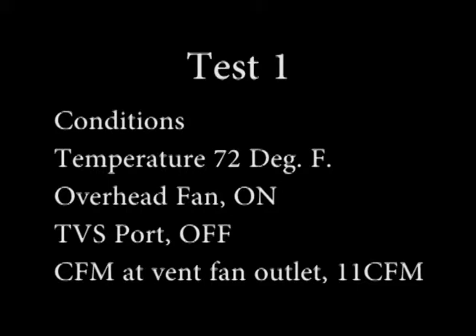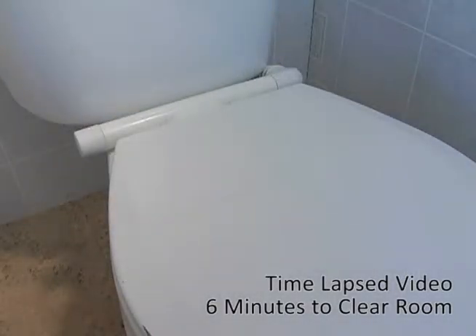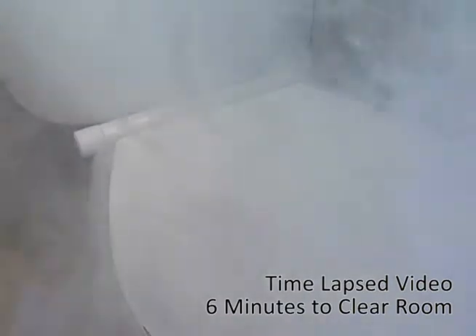Test 1. Test 1 simulated the standard configuration with a ceiling-mounted fan. The TVS system was not in operation for this test. The test smoke entered the test chamber through the toilet bowl. It first filled the bottom of the test chamber and eventually filled the entire chamber with smoke. The smoke injection was then suspended.